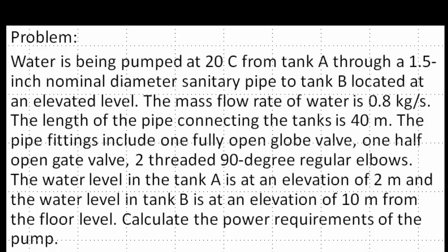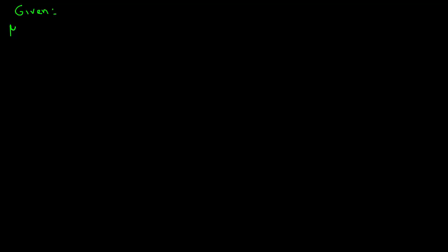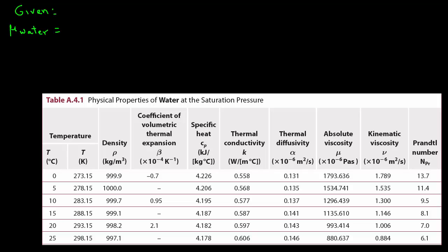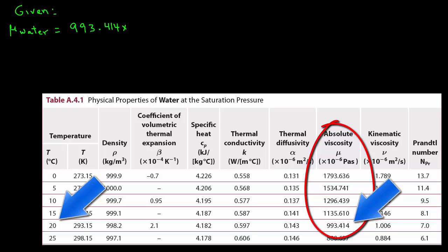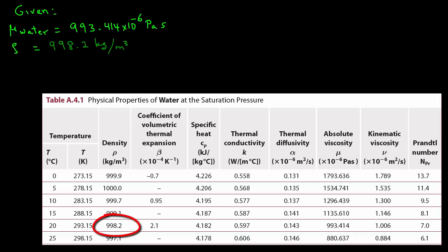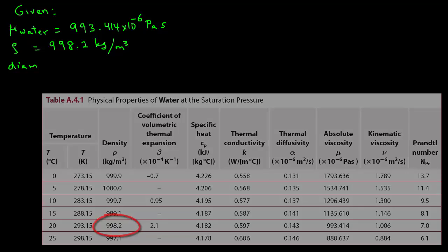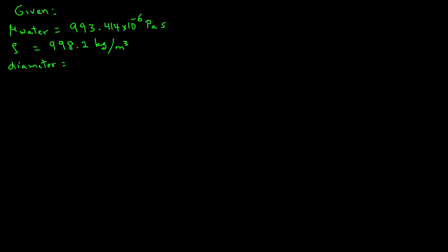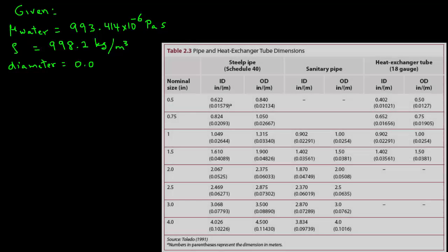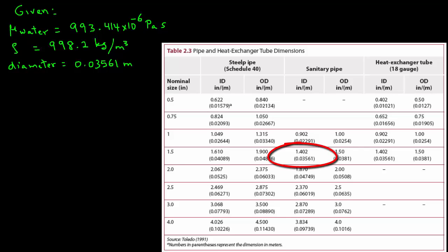We are to calculate the power requirements of the pump. We will use a table to determine the viscosity and density of water at 20 Celsius. From the table, the viscosity of water is 993.414 × 10⁻⁶ Pascal seconds. The density is 998.2 kilograms per cubic meter. The diameter of the pipe is 1.5 inch, which is equivalent to 0.03561 meters.